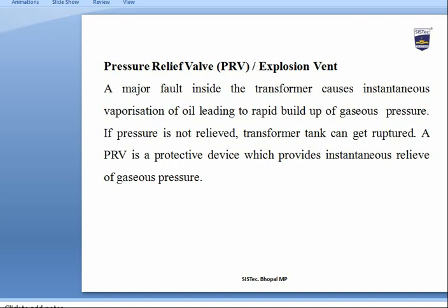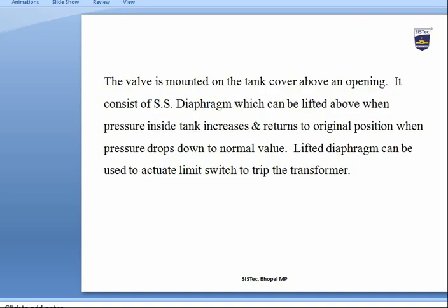The Pressure Relief Valve (PRV) or explosion vent protects against major faults inside the transformer, which cause instantaneous vaporization of oil leading to rapid buildup of gas pressure. If pressure is not relieved, the transformer tank can rupture or explode. The PRV provides instantaneous relief of gas pressure; it consists of an SS diaphragm which lifts when pressure inside the tank increases and returns to its original position when pressure drops to normal.